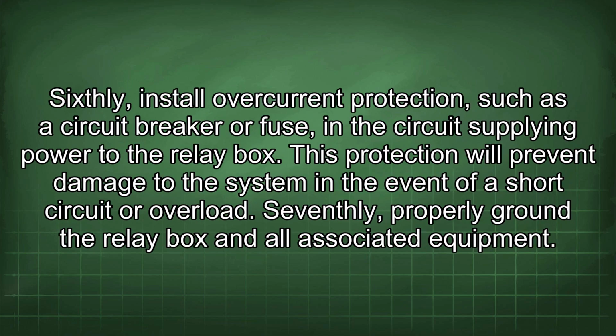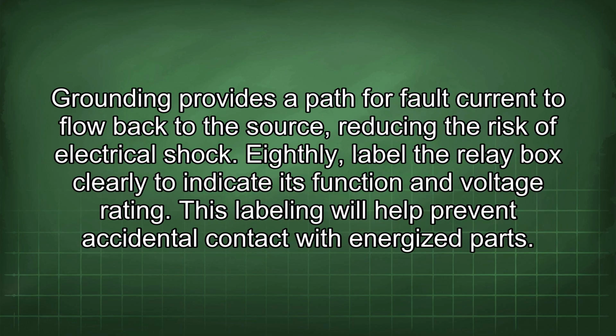Sixthly, install overcurrent protection, such as a circuit breaker or fuse, in the circuit supplying power to the relay box. This protection will prevent damage to the system in the event of a short circuit or overload. Seventhly, properly ground the relay box and all associated equipment. Grounding provides a path for fault current to flow back to the source, reducing the risk of electrical shock.